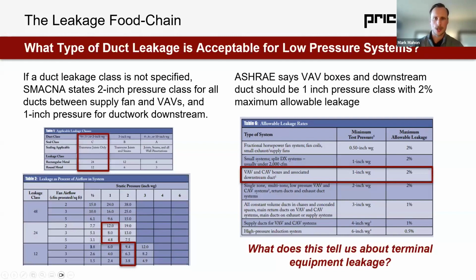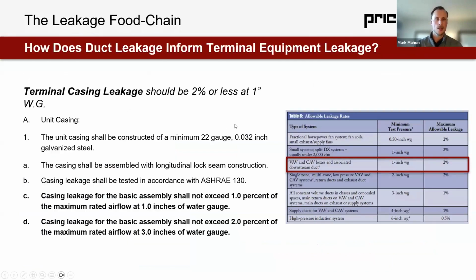And so what does that really tell us about terminal equipment leakage specifically? Well, that tells us terminal casing leakage should be 2% or less at 1-inch water gauge. And that is really what feeds into most manufacturers' specifications. So I have the Price terminal specification on screen here on the left. And what we can see is casing leakage for the basic assembly should not exceed 1% of the max rated airflow at 1 inch water gauge. So when we're looking at that 2% recommendation from ASHRAE, we're saying 1% for the VAV box, 1% downstream. That is maybe not ideal, but that is how all manufacturers tend to do it.